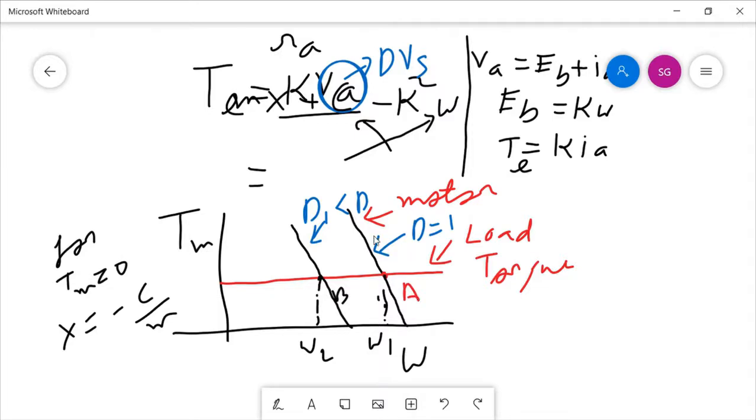But when we talk about AC drives, in an AC motor like a three-phase induction motor, there is no decoupling between the field winding and armature winding. There is one single winding, that is the stator winding, and the second is the rotor winding. So the magnetization current and the load current both have to flow from the same winding, the stator winding. Therefore, there is no decoupling between these two, and if you vary one of them, then the second is also affected. So we can study that in detail.